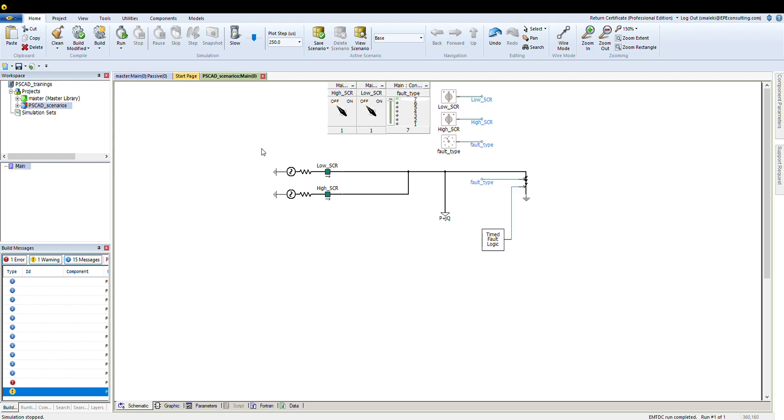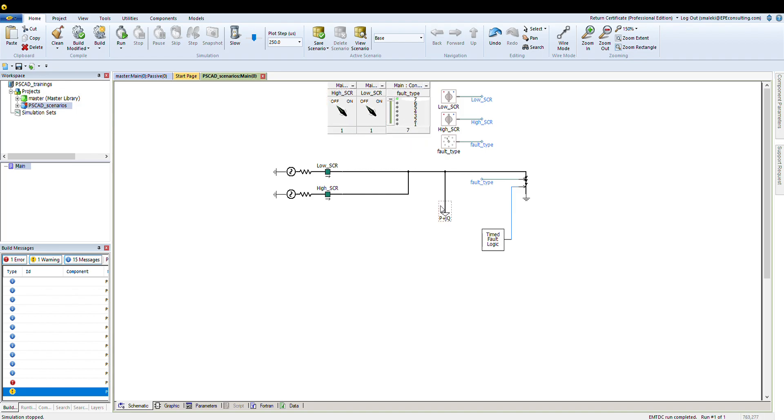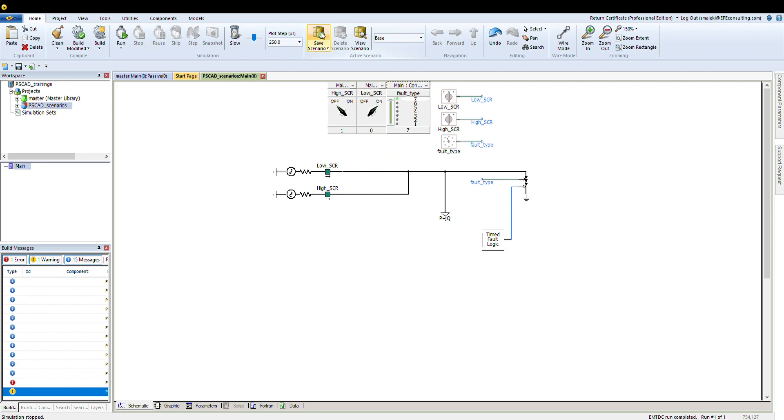For the first scenario, let's say I want to test the low SCR ratio and I don't want the high short circuit ratio to be in the system operation. I want to apply a three-phase fault. So I set my fault case at seven, which is defined for the three-phase to ground fault type. I don't want to have my high SCR as the network, just the low SCR.